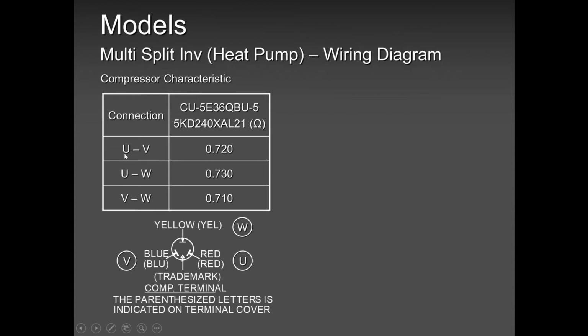Compressor, a guy will call me and say, Paul, between U and V, U and W, V and W, I'm getting the same ohm reading. But why are you telling me the compressor is bad? That means the compressor windings are good, but the compressor is stuck, mechanically stuck. So it's throwing an error saying that the compressor is defective. So when the compressor is defective, it could be either the windings, which you will find different readings on, or you will find the same readings, but it's stuck mechanically.